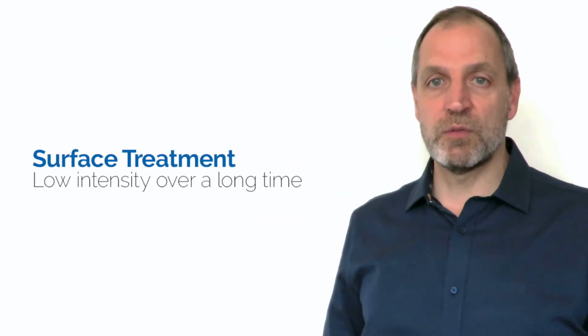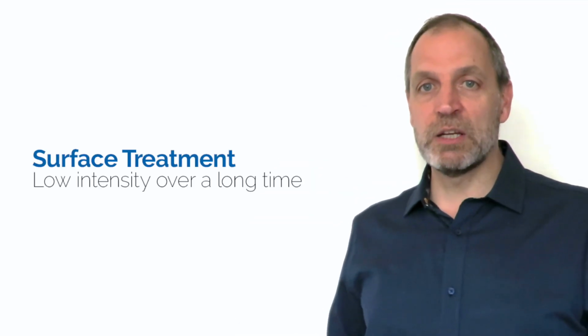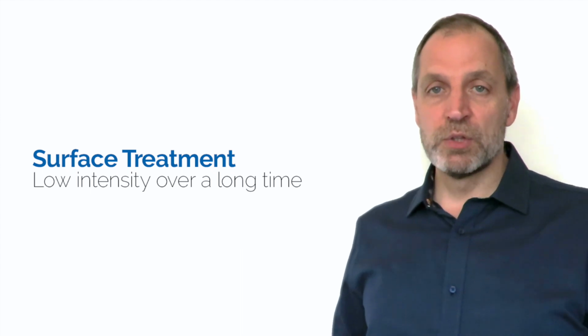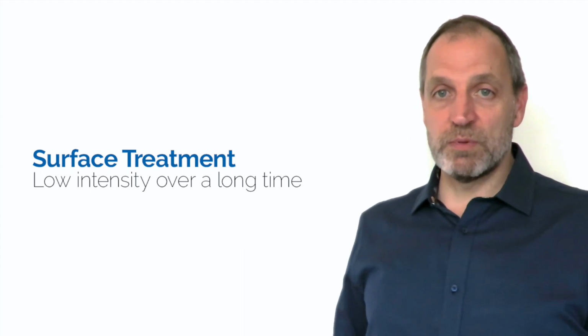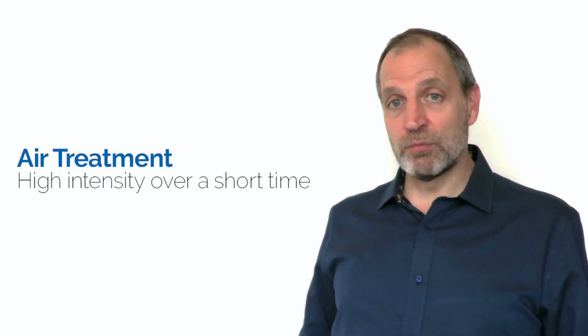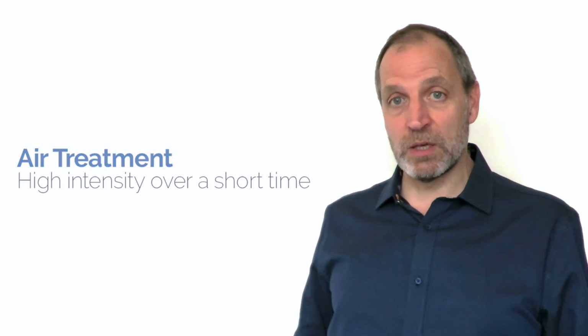So generally speaking, if you're treating a surface, for example a heat exchange coil, you need relatively low UV intensity, but this is over a long period of time. Whereas for air treatment, you need a really high intensity UV because the air is moving very quickly over the UV. So it's really the difference between a candle and a blowtorch in a sense, the effectiveness of these systems. So UVC intensity, UVC dosage is really important.